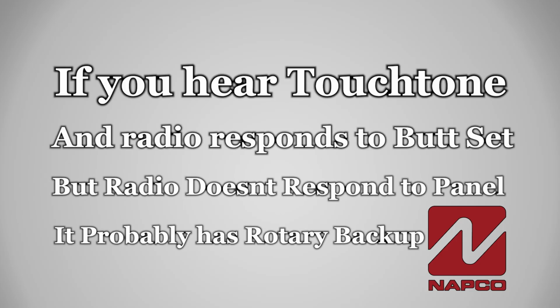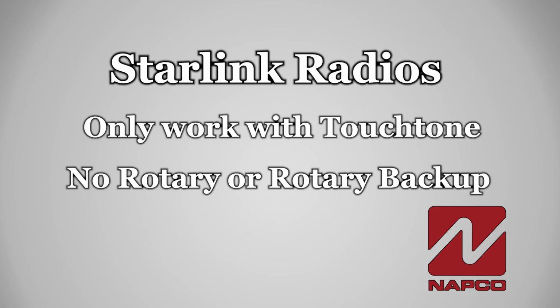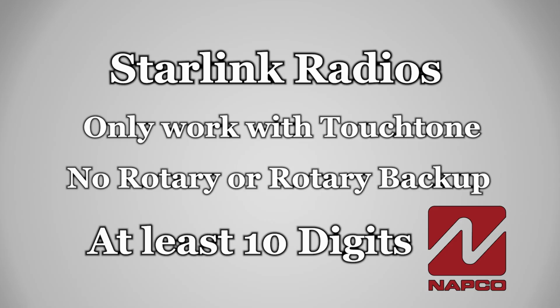Also, if you hear touch tone from your panel and the radio doesn't respond with a handshake, but it does respond to your butt set, this could mean that the panel has a rotary backup setting. So verify your panel's programming.